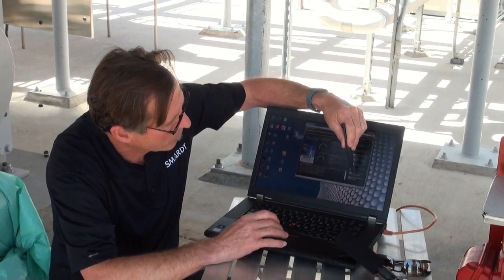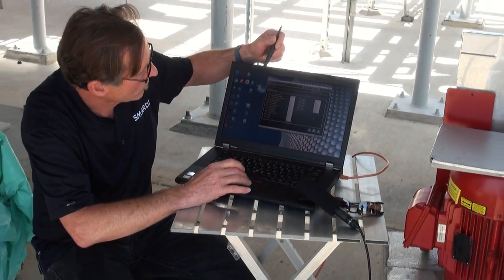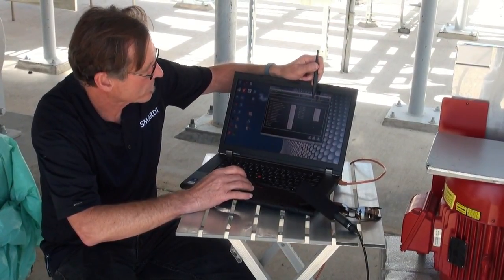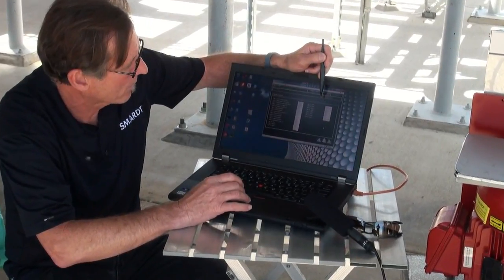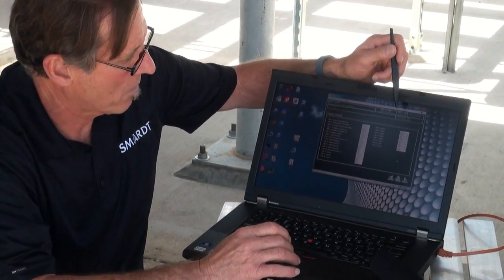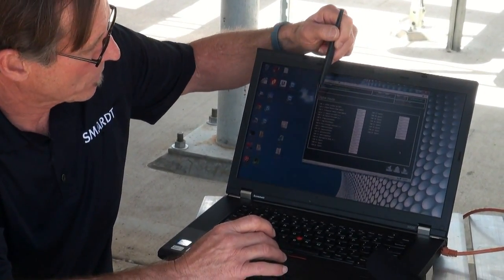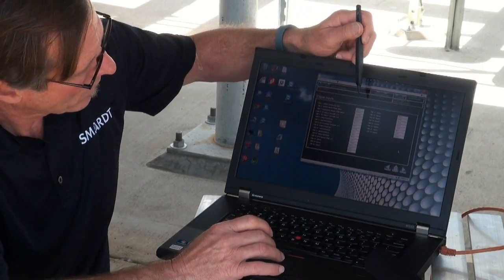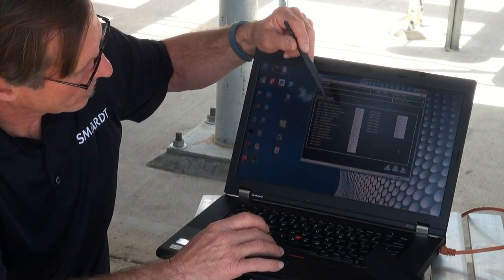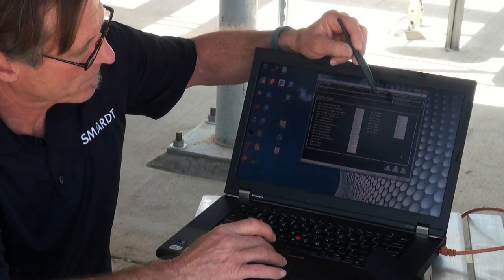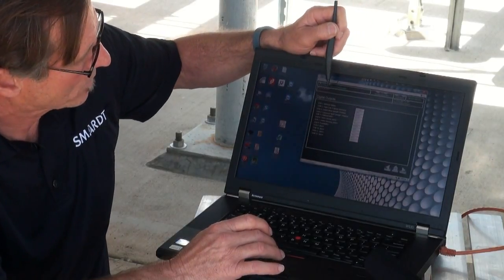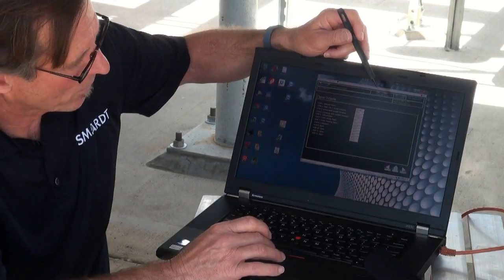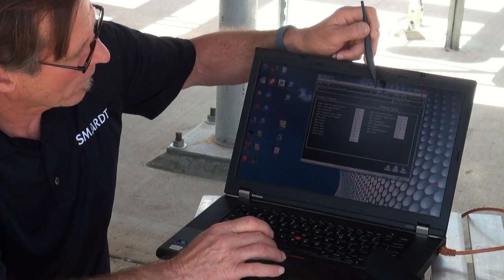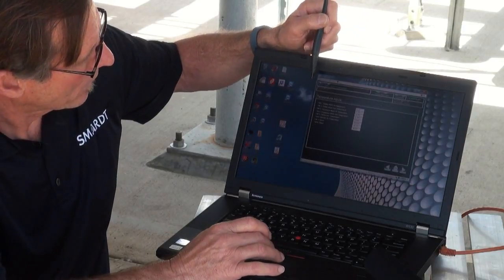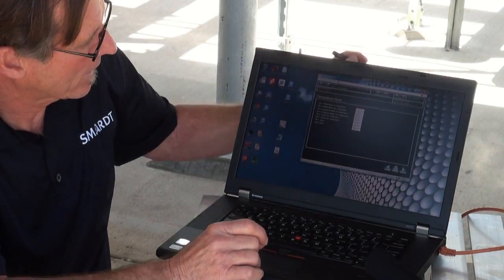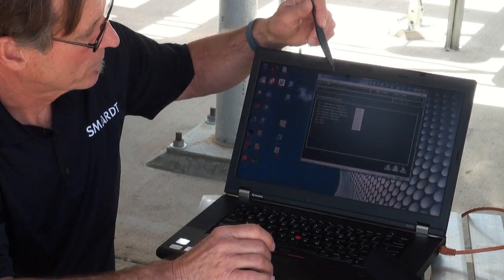That's pretty much it. We've got an input-output page. This shows you all your inputs and outputs. This is a digital input screen we're looking at here, and it's everything without the graphics. So it's all the same information without the graphics. So you see your chill water in and out, condenser water in and out. There's a number of spares as well. But it's all the information that we've been going over without the graphics. And then we can scroll over. We've got digital outputs. So it's just another reference. Analog outputs and temperature inputs. So it kind of puts everything for diagnostics. It's nice to have everything side by side on one page.